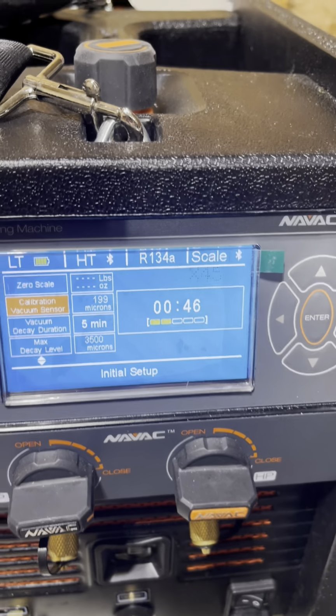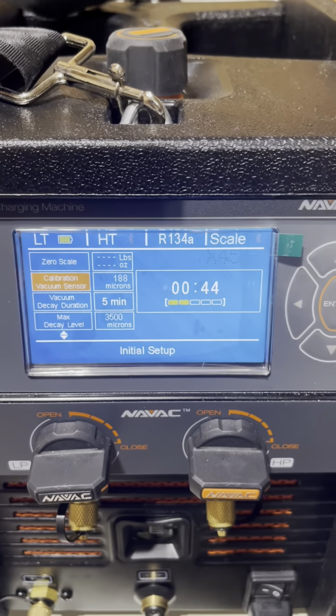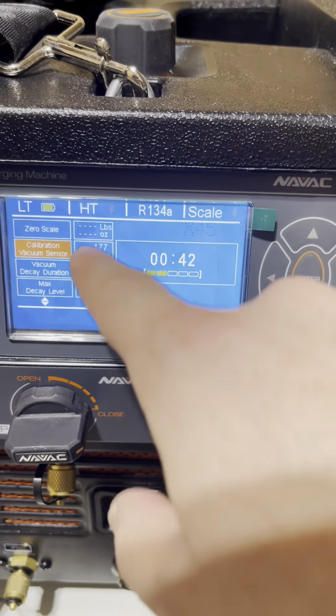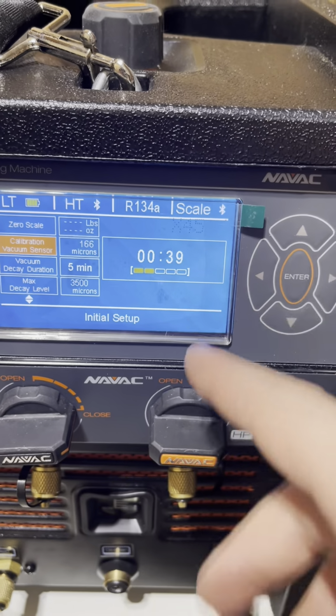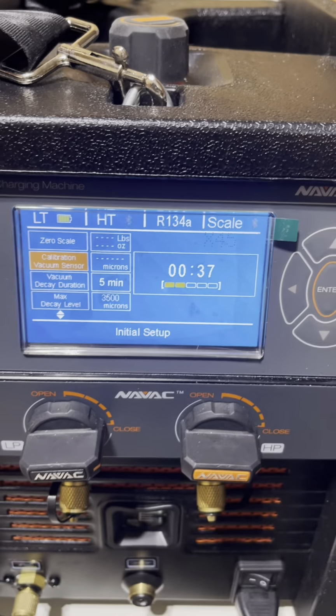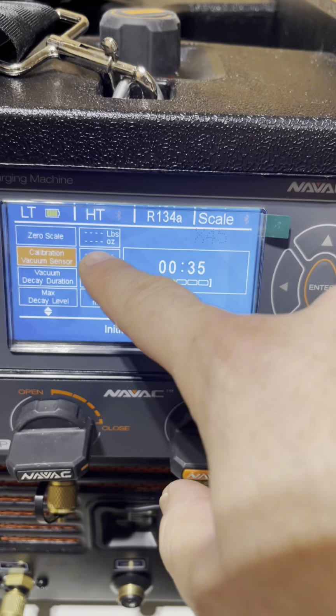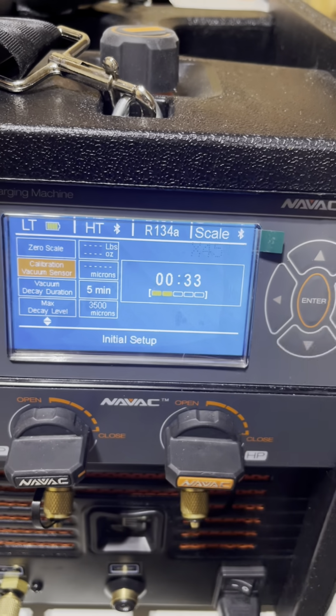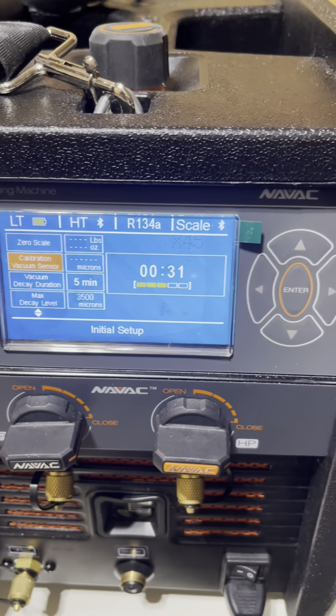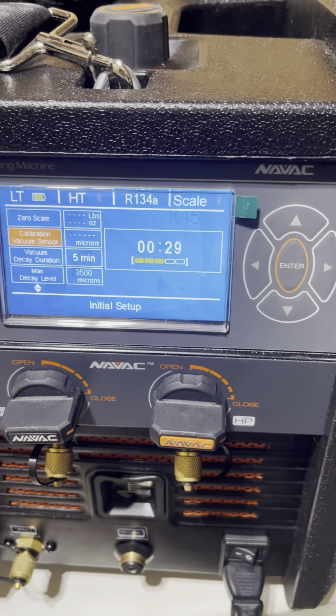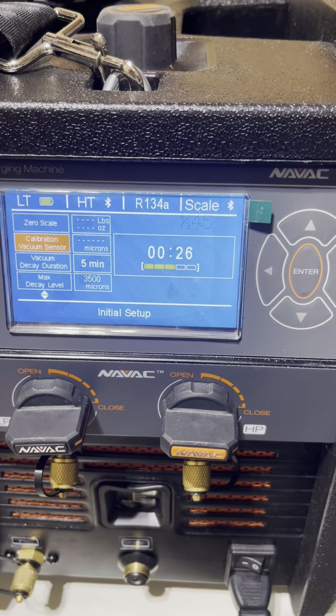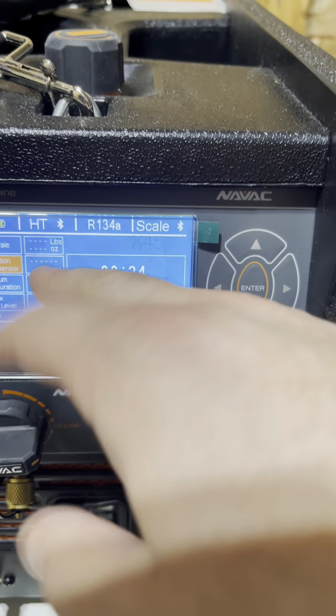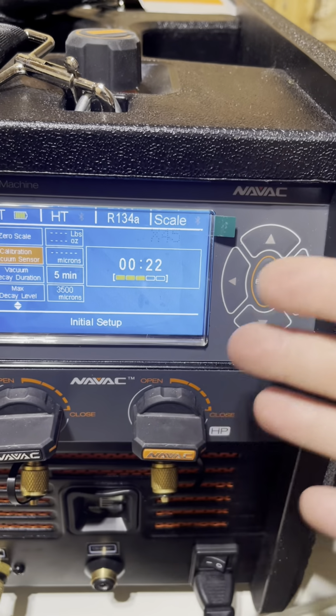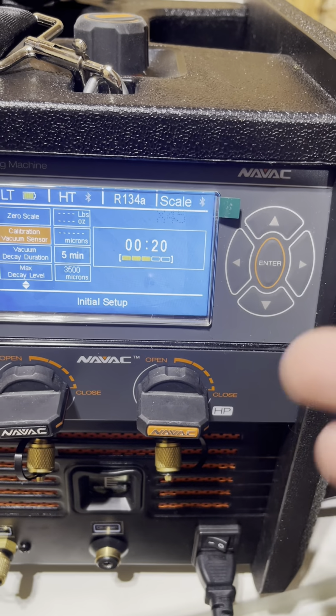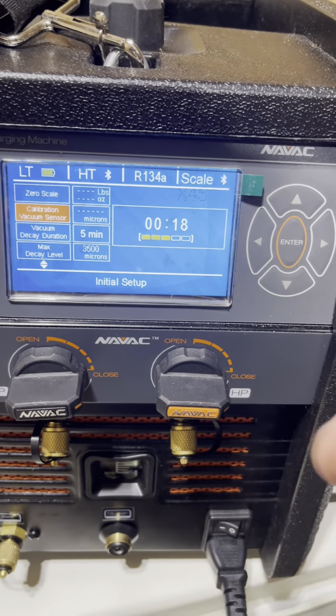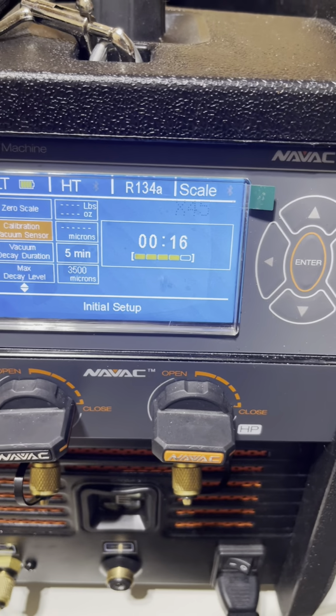It will go down, it will finish it up, and then it will pretty much, see, now it's doing the calibration. It looks like it's zeroing it out, so that's what it's doing. And it takes about a minute and a half. So basically, if you feel like the pressure that you're getting as feedback from the compressor or the system inside is not accurate, you can calibrate your vacuum sensor.